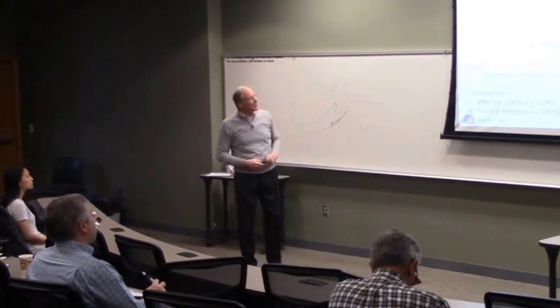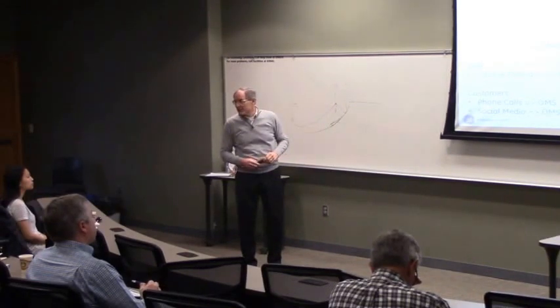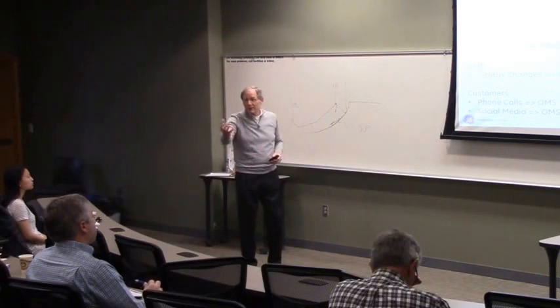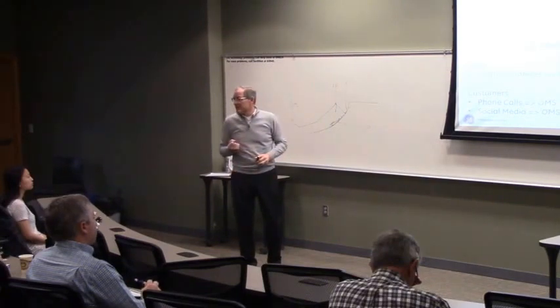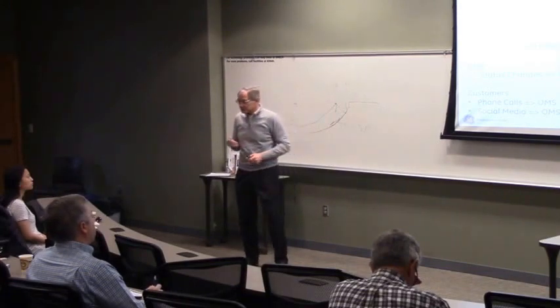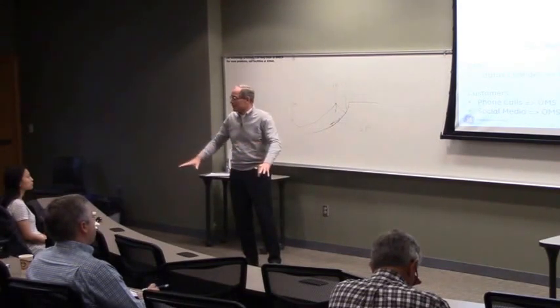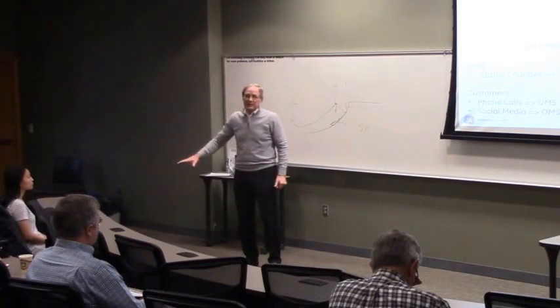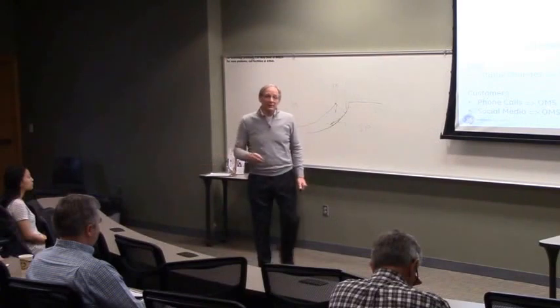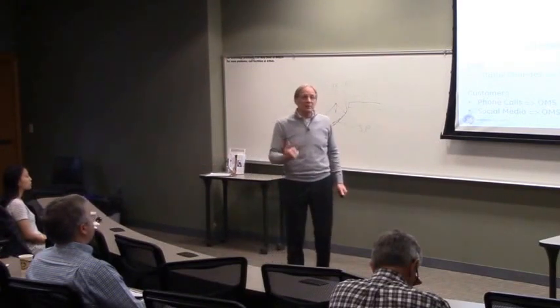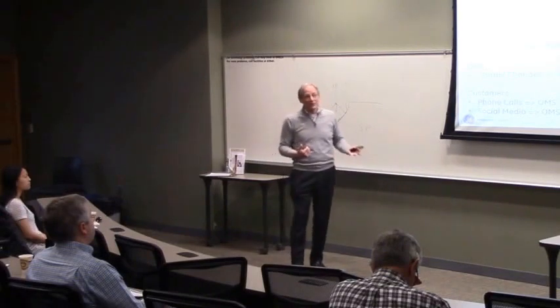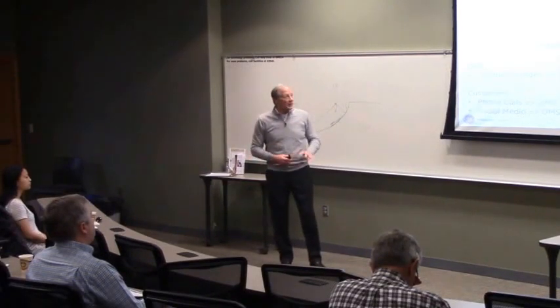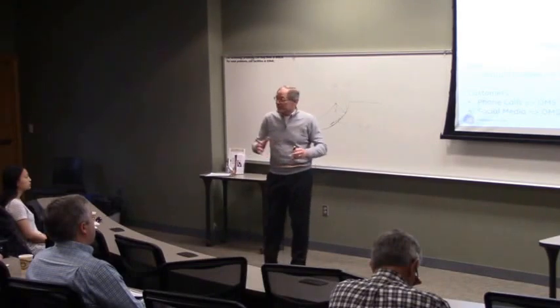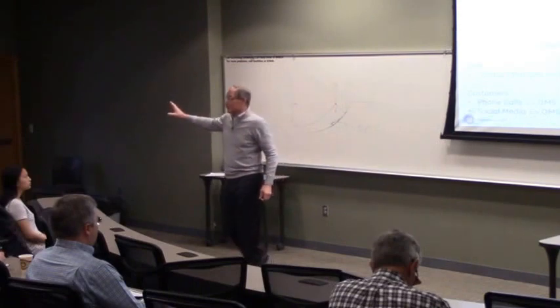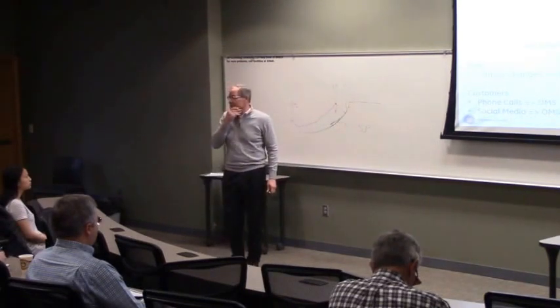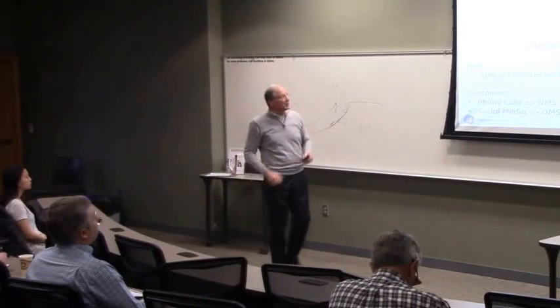So one thing with meters is we can take the voltage from certain smart meters. We can ping those through the network and bring that information into the network model, the DMS. So when we do volt-var control, we want to flatten the voltage profile and lower it. But we have a standard in the United States that says the voltage at the customer's premise must be 120 plus or minus 5%. They need to be within, right, 126, 114 volts. We don't want to get too close to 114. Okay? So if we have a real long feeder with a lot of voltage drop, then we may have a problem when we do volt-var control. Okay? So we need to monitor that. We can use smart meters for that.